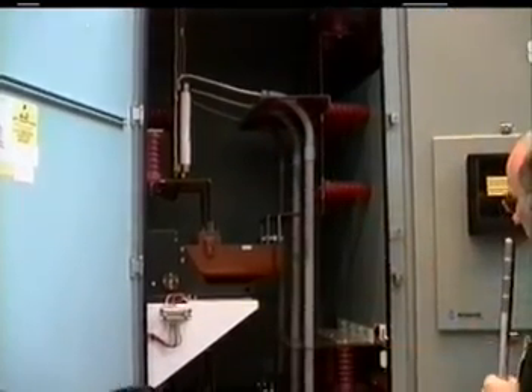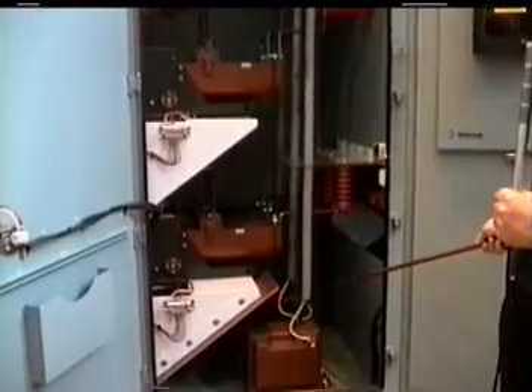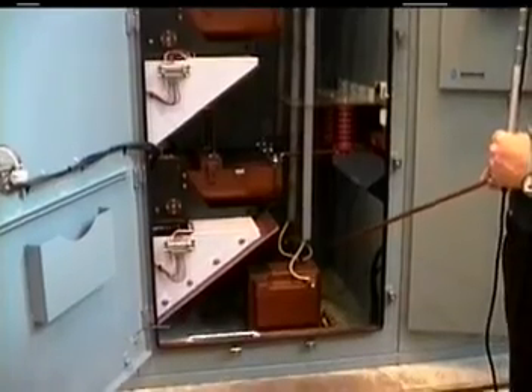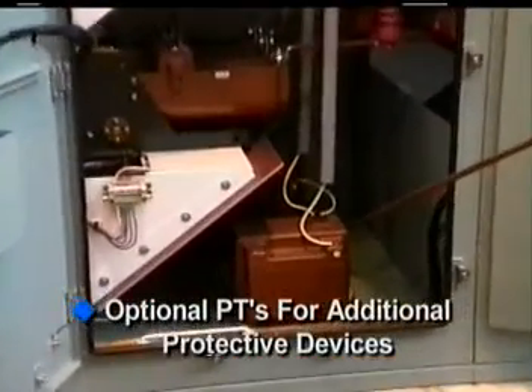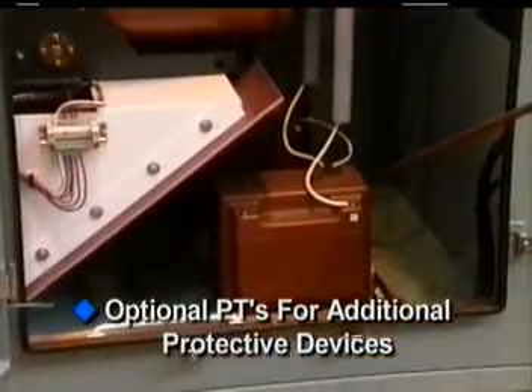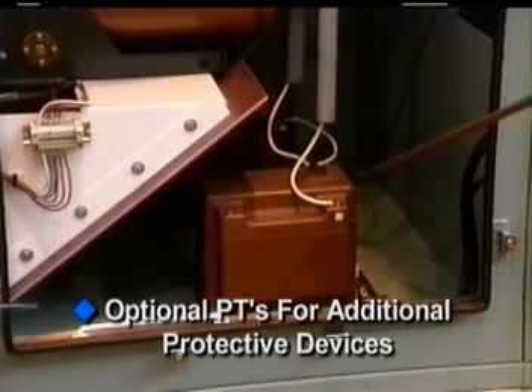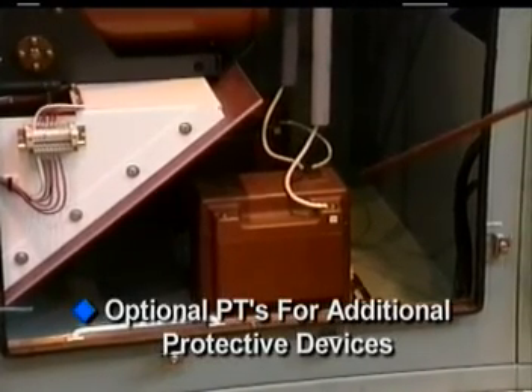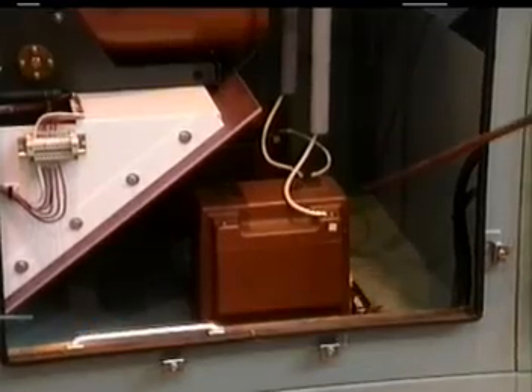Then we can pick off of the output side or the load side of the fuses and come down here to the PTs. The PTs in the system are used with the Multilin to provide for phase voltage protection, low line, high line, voltage imbalance, and for metering purposes within the Multilin.